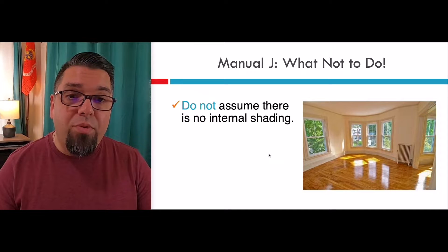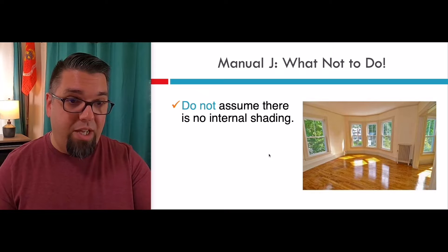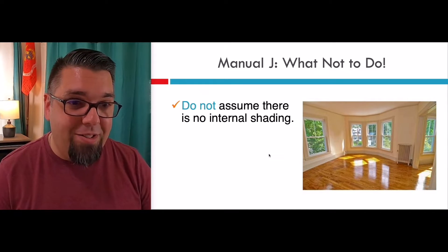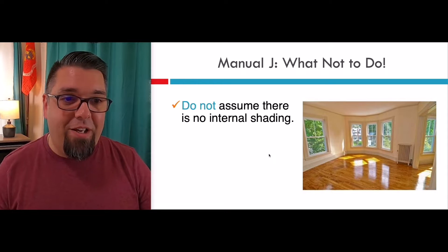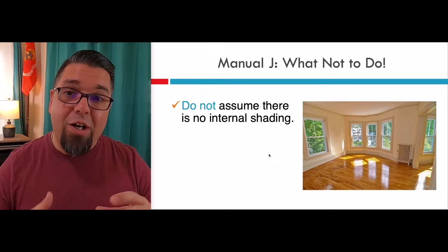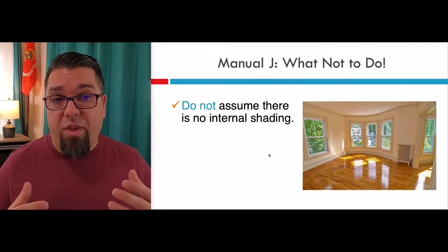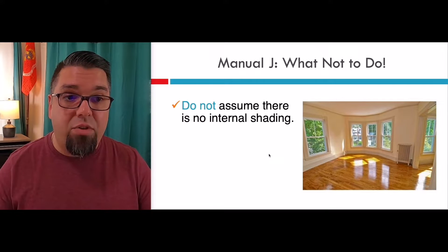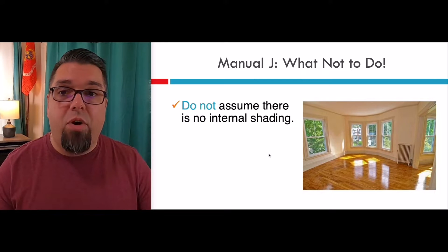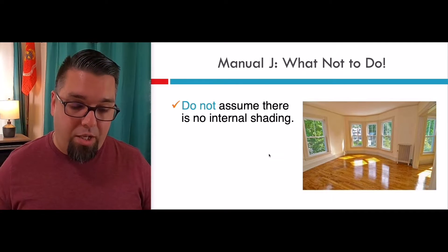Don't assume there's no internal shading — even on new construction. If you do the loads without accounting for shading, the cooling gain is going to be much higher than when you include insect screens and drapes or medium shades half-drawn. Really important: don't assume there's no internal shading.